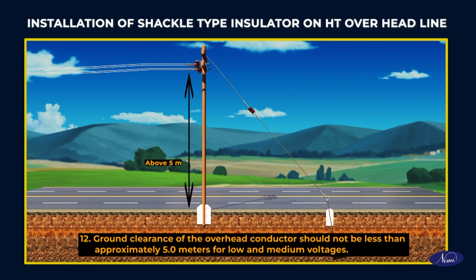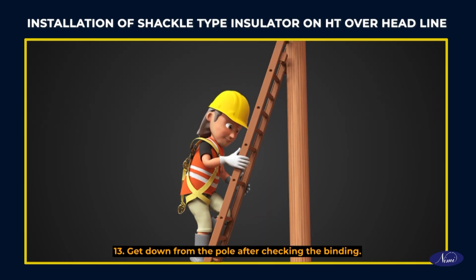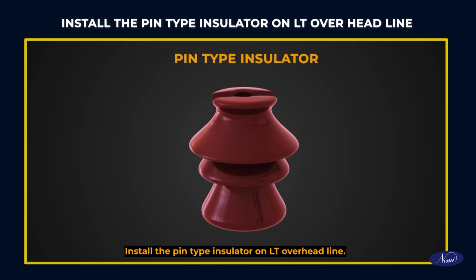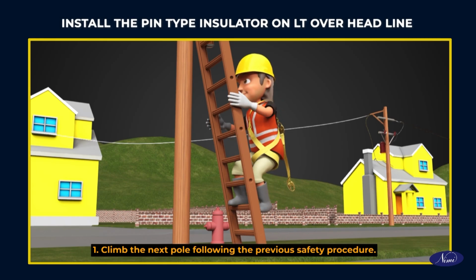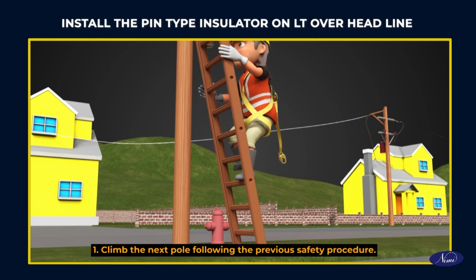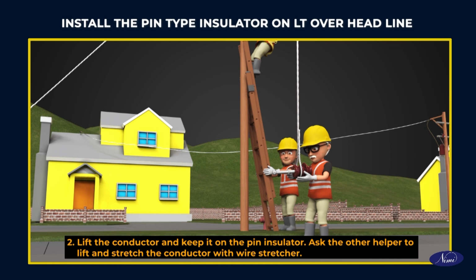Note: ground clearance of the overhead conductor should not be less than approximately 5 meters for low and medium voltages. Get down from the pole after checking the binding. Install the pin type insulator on LT overhead line. Climb the next pole following the previous safety procedure. Lift the conductor and keep it on the pin insulator.